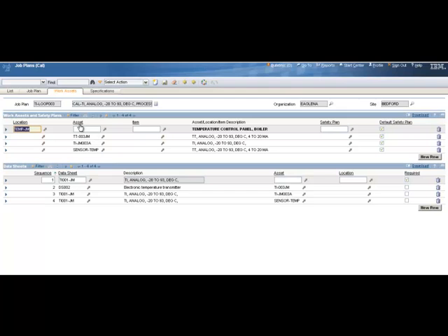If, for example, that loop calibration fails, then I have to find out what component within that loop was the failing component. By associating with the loop up here, the loop data sheet, I also associate each individual component's data sheet as well. And you notice that only one of these is required. The loop calibration has its own data sheets required.